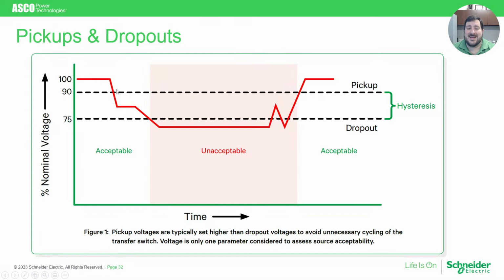dropout value, it does not necessarily mean that when you exceed your dropout value, which is the point at which your source is considered bad or unacceptable power for your loads, it does not immediately consider it good the moment it crosses that same threshold again. And the reason is because if the power is sitting right at that level and bouncing just above and below it, you do not want to constantly be transferring the equipment back and forth, or starting and stopping the generator. So there is actually a gap between declaring the source bad at your dropout and a significant improvement before it is considered good again, which is your pickup.